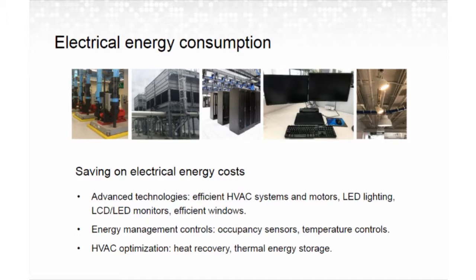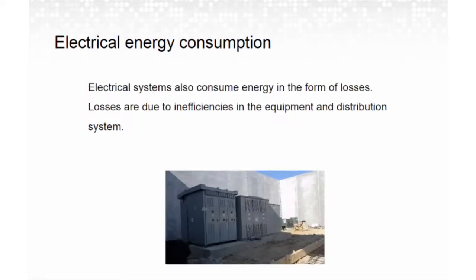They also talk about energy management systems, ways to shut off the equipment if it's not being used, such as occupancy sensors, maybe temperature controls. We also talk about HVAC optimization, so heat recovery, utilizing some of that heat we're taking out of the system, maybe thermal or energy storage, producing ice in the off hours at less cost so you can use it during peak hours. What they don't tend to talk about is the electrical distribution system itself.